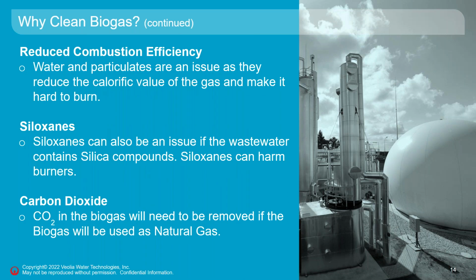It's very common that water or moisture and other particulates are present in your biogas, and these particles and water vapor actually reduce the calorific value of your gas and make it difficult to burn. So we need to remove those particulates and water vapor from biogas. And if you have silica compounds in your wastewater, siloxanes can be formed and can be present in your biogas, and it is actually an organosilicon compound that can harm your waste gas burners.